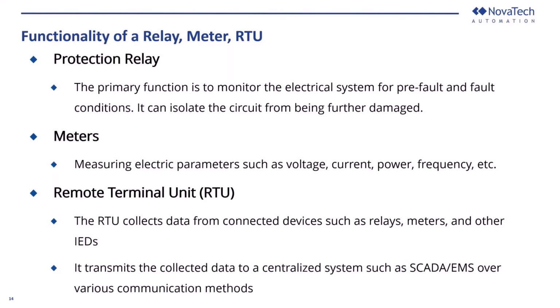Let's start. The protection relay's primary function is to monitor the electrical system, typically finding pre-fault and fault conditions, so it can isolate the circuit from being further damaged. That's the main purpose for it.